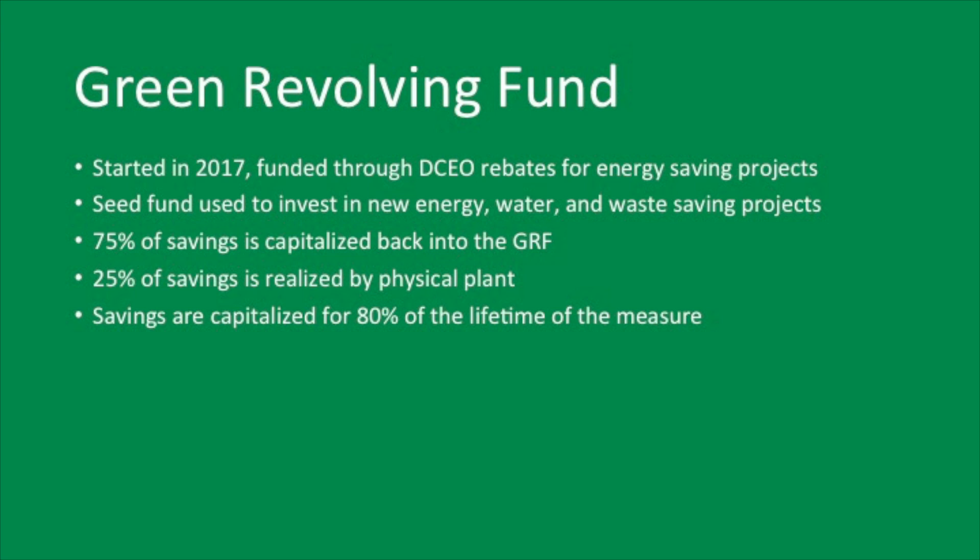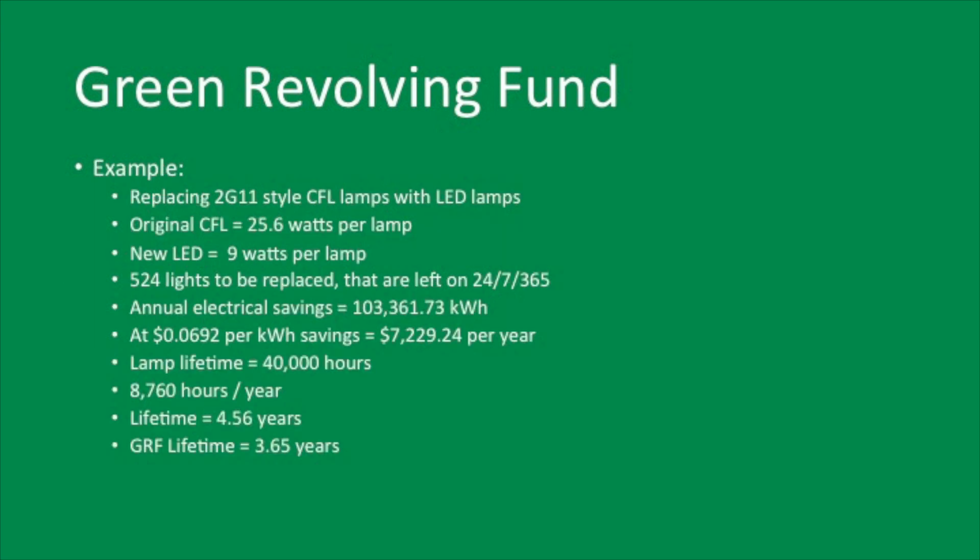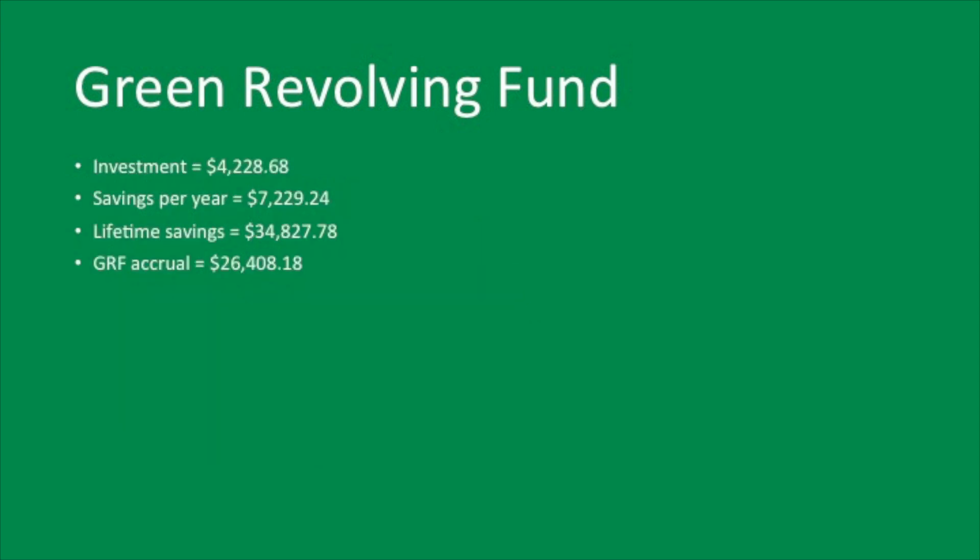75% of our savings are capitalized back into the fund and 25% of savings is kept with the physical plant. Savings are counted for 80% of the lifetime of the measure. For example, we're replacing 2G11 CFL lamps — the little square white fixtures you see in the stairwells. The original is 25.6 watts, the replacement is 9 watts, and there are 524 lights to be replaced. Annual electric savings are 100,000 kilowatt-hours, about $7,000 per year. Our investment is $4,000, and over the bulb lifetime we save $34,000 — so $26,000 goes back into the GRF fund to be reinvested into new savings projects.